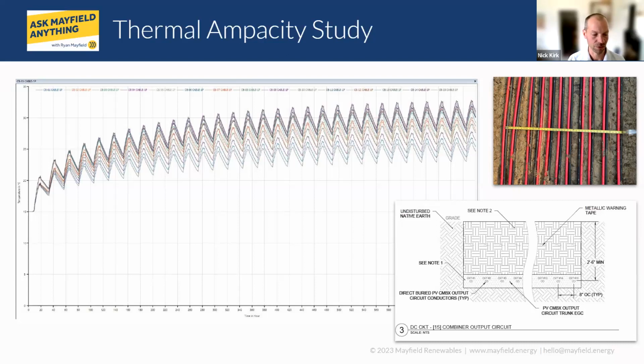Yeah, so our analysis was over a 30-day time period, and we basically ran the study a few different ways to determine where in the year the highest conductor temperature would be, because as we're aware, some really cold and sunny days in the springtime can produce a lot of PV energy. But because the average soil temperature during those months is pretty low, we found that the worst case was actually closer to the middle of summer for this particular site. It's all site dependent, right? So it's based on soil conditions, environmental conditions, and then all the inputs from the design that we're incorporating into the model. Right. Yeah, that was the part where the geotech gets involved. So there's a lot to it.